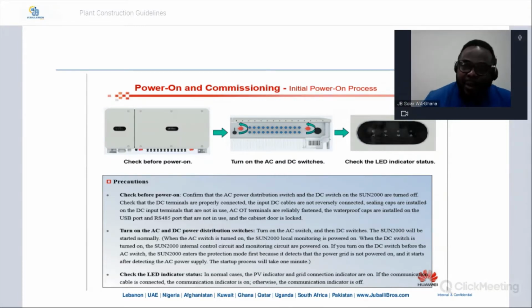All right, so let's jump into some installation, some commissioning, and some powering on units. Installation of the inverter is basically mounting the inverter on a wall or on any mounting system that you have been provided with. If it's a metal mounting system or a concrete one, there's always a mounting bracket in the inverter system. You just mount it on the wall, put in your screw expansion system, and then you mount the inverter, connecting the DC cables to the bottom of the inverter, as we mentioned. So these are the MPPTs from here. You can see them clearly, right? So you terminate them directly. You don't need the DC combiner box, and then you are good to go.